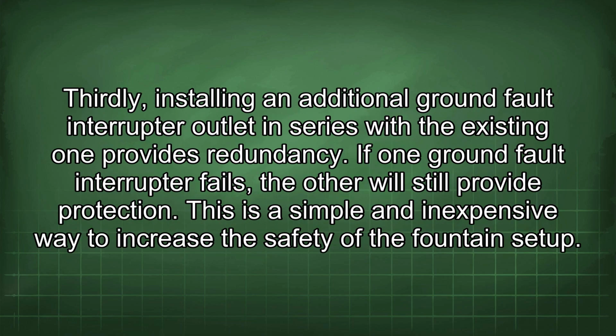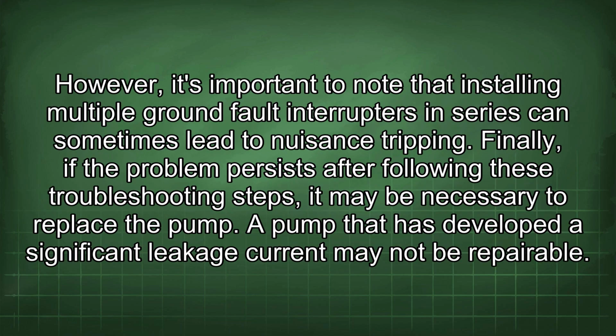Thirdly, installing an additional ground fault interrupter outlet in series with the existing one provides redundancy. If one ground fault interrupter fails, the other will still provide protection. This is a simple and inexpensive way to increase the safety of the fountain setup. However, it's important to note that installing multiple ground fault interrupters in series can sometimes lead to nuisance tripping.